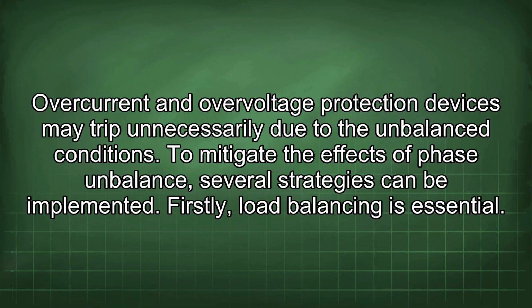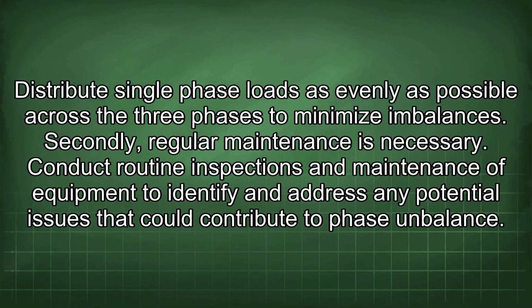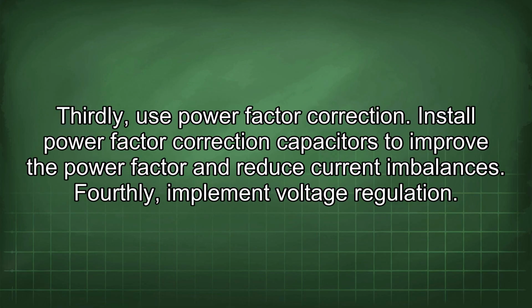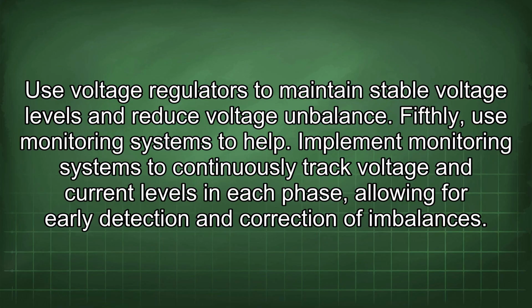To mitigate the effects of phase imbalance, several strategies can be implemented. Firstly, load balancing is essential. Distribute single-phase loads as evenly as possible across the three phases to minimize imbalances. Secondly, regular maintenance is necessary. Conduct routine inspections and maintenance of equipment to identify and address any potential issues that could contribute to phase imbalance. Thirdly, use power factor correction. Install power factor correction capacitors to improve the power factor and reduce current imbalances. Fourthly, implement voltage regulation. Use voltage regulators to maintain stable voltage levels and reduce voltage imbalance.